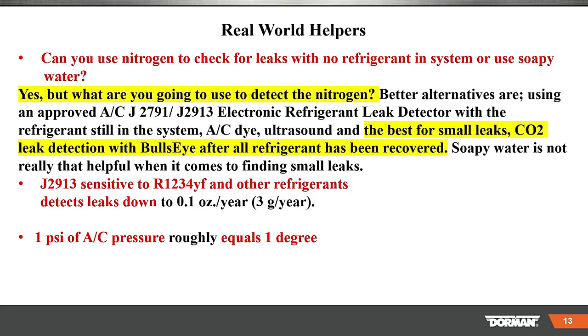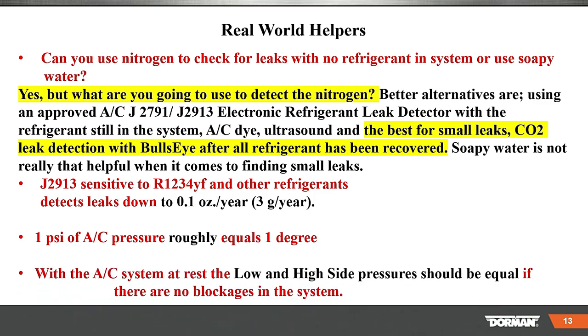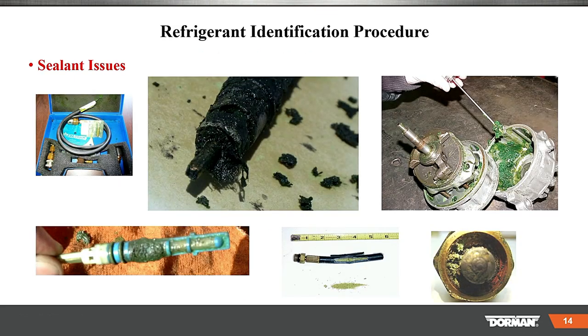1 pound of AC pressure roughly is 1 Fahrenheit. Roughly 1 Fahrenheit, okay? With the AC system at rest, low and high should be equal. We've seen that on the machine. If they're not equal, you got a clog somewhere, an important step.